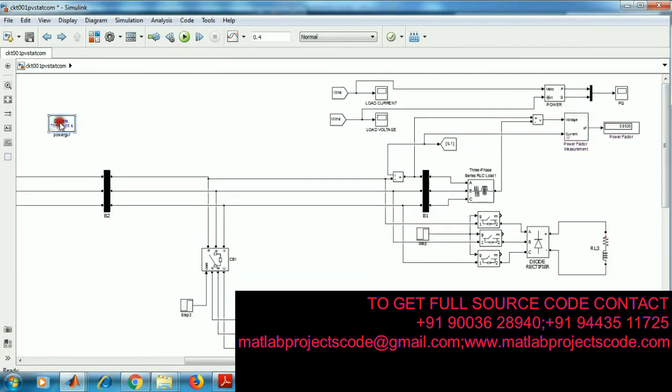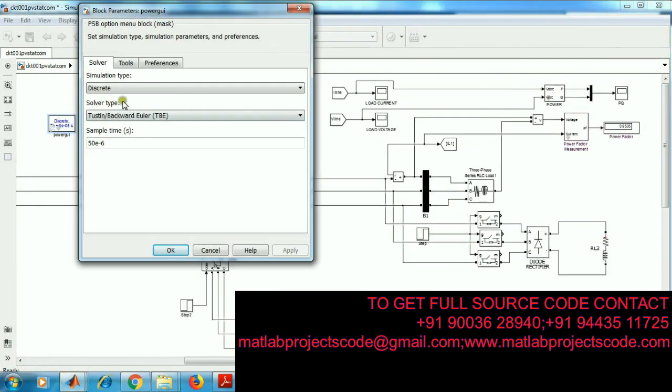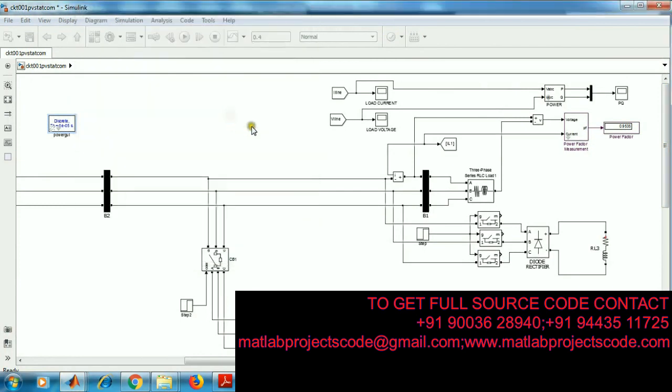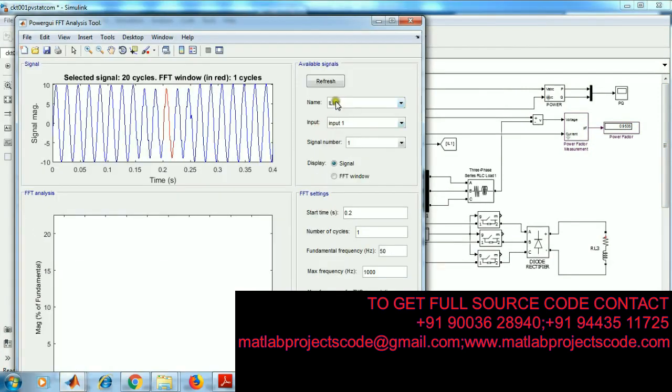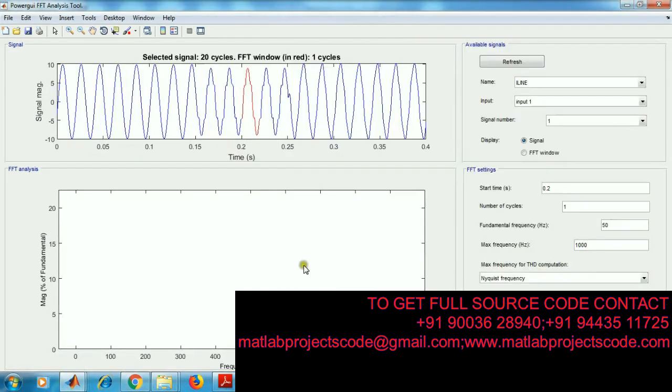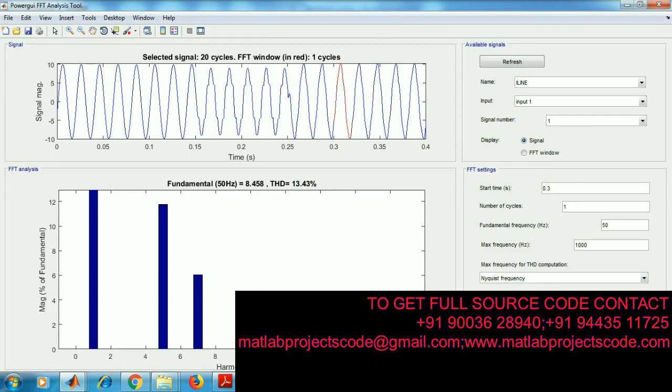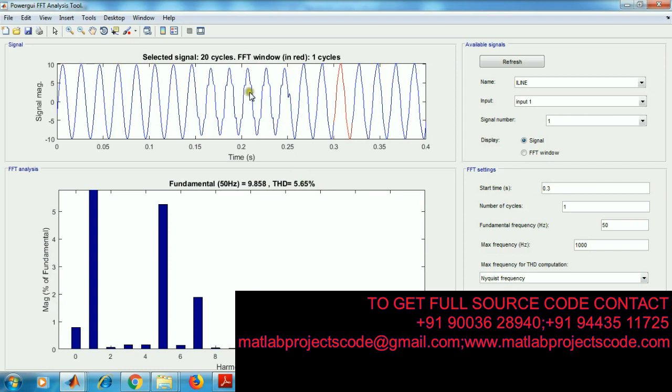So we will see the FFT analysis. Current when connecting load, harmonic and distortion will be high. After connecting STATCOM, we get 5%. When connecting load, the THD will be high. After connecting STATCOM, the THD will be low.